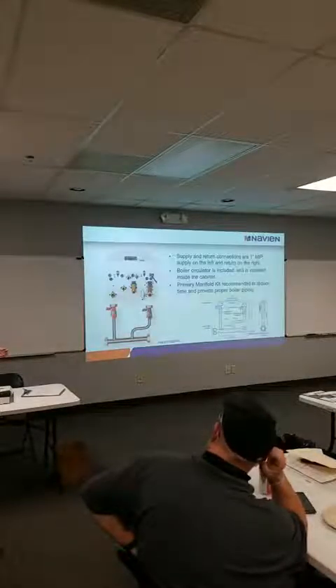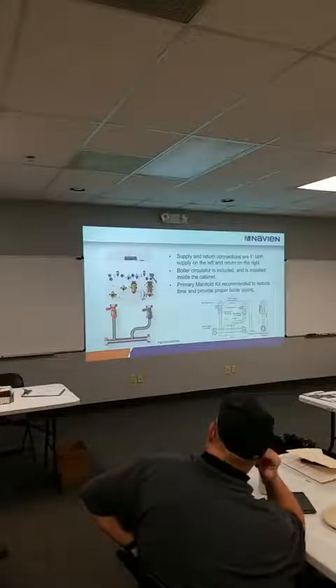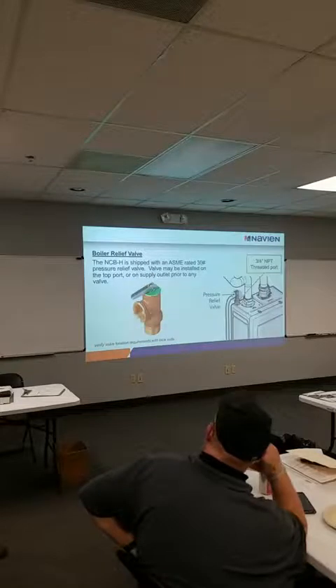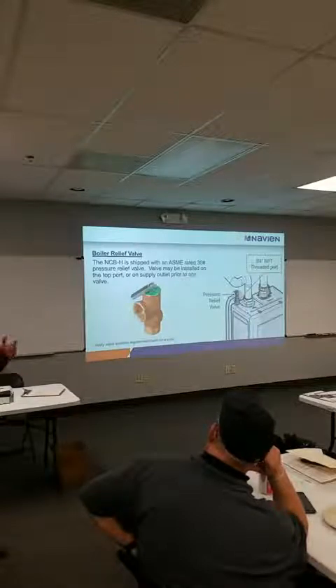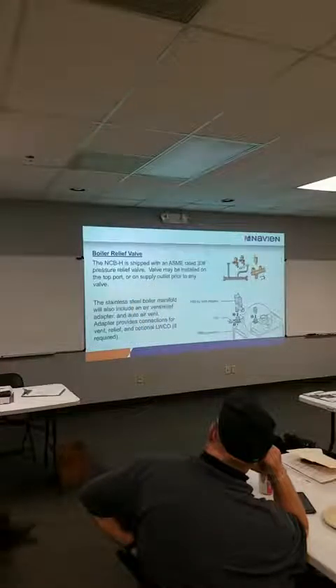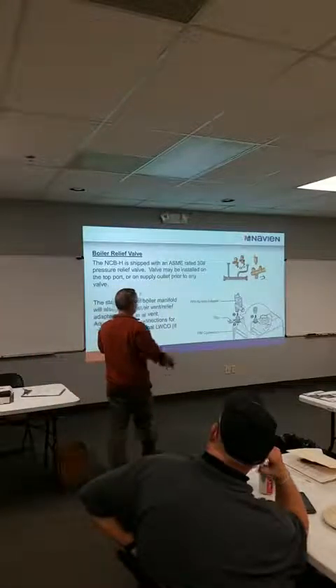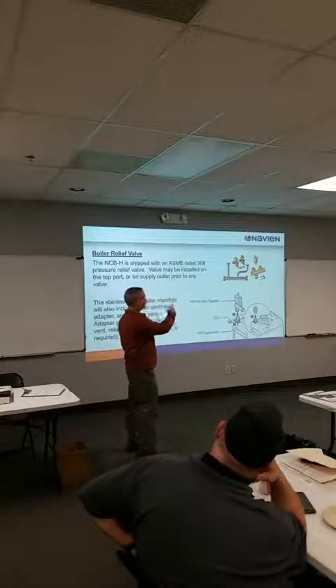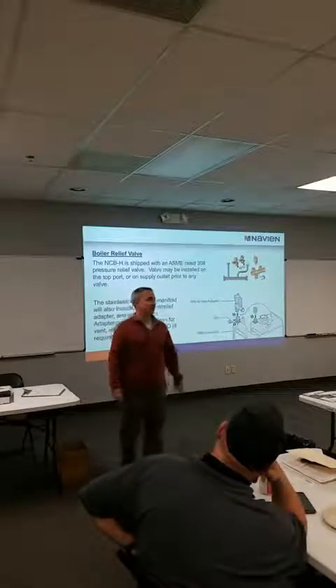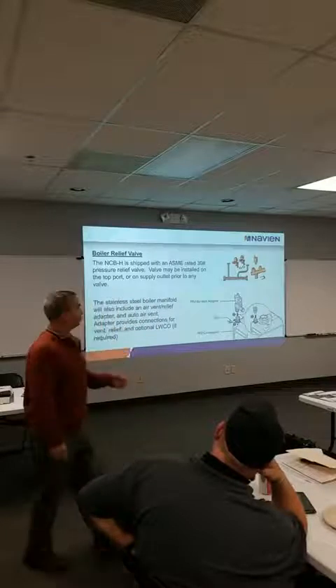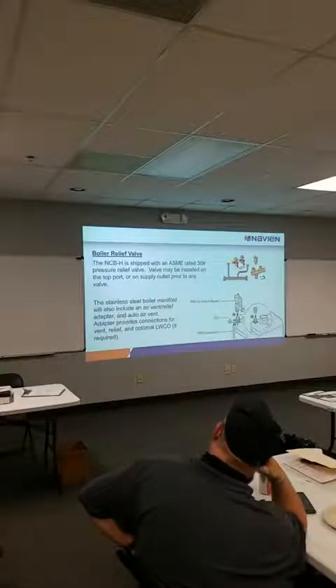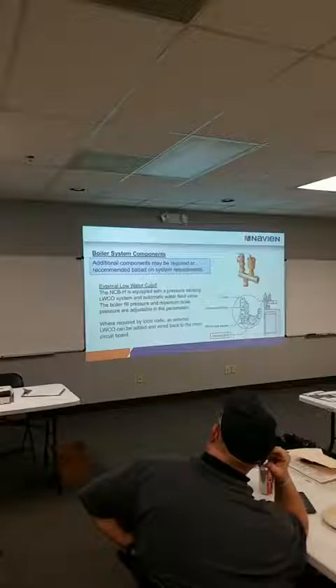That's what our manifold looks like. We make that manifold stainless steel. It unions right up to the bottom of the unit. Relief valve, it's got a port on top again for a relief valve. You can leave that relief valve off as you're filling the boiler up, and once water starts dumping out of the top, you're full and you can put that on. If you buy our manifold, it comes with that T-bar that I've shown you in a number of pictures, where you can tee in an air vent and the relief valve. It's also got an outside port for a low water cutoff, which you see on the end there.